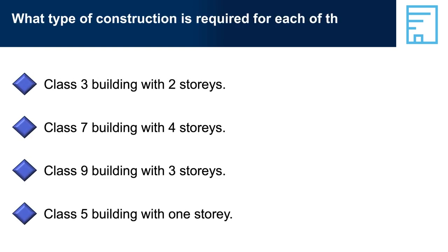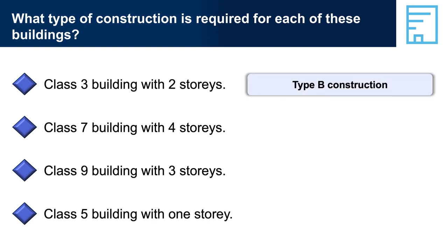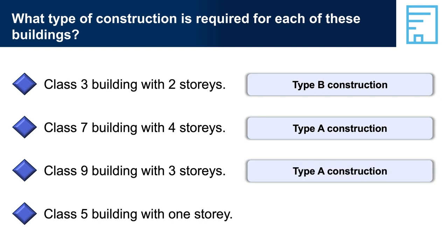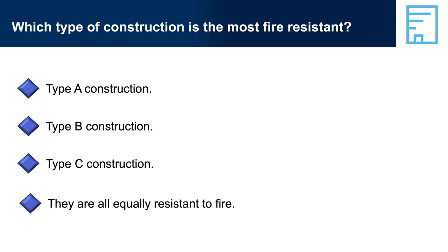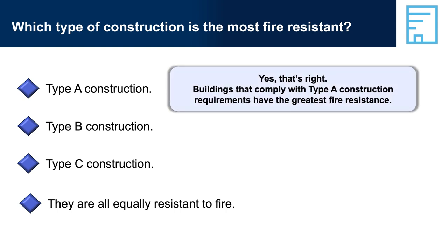What type of construction is required for each of these buildings? A Class 3 building with two storeys is Type B construction. A Class 7 building with four storeys is Type A construction. A Class 9 building with three storeys is Type A construction. A Class 5 building with one storey is Type C construction. Which type of construction is the most fire-resistant? The correct answer is Type A construction — buildings that comply with Type A construction requirements have the greatest fire resistance.